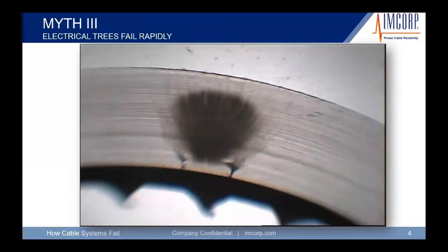Another myth is that carbon trees will go immediately to failure. Here we have a combination of a water tree and two carbon trees. These carbon trees, we know today and have been able to study over the last 10 years, have intermittent growth. They don't just show up and take the cable to failure. As you can see, this particular cross-section hasn't gone to failure, and you see a water tree with it and then the two carbon trees.